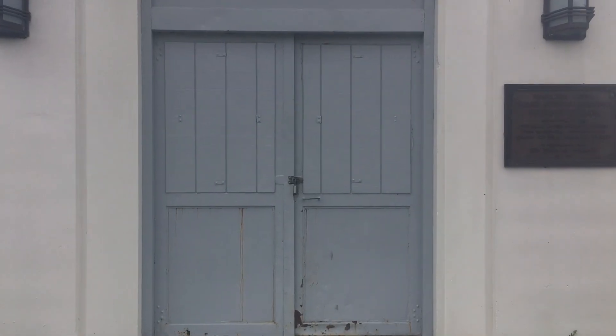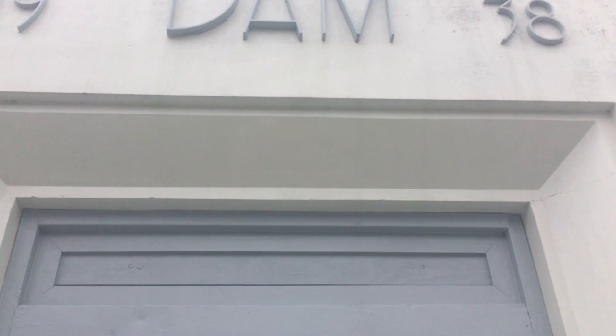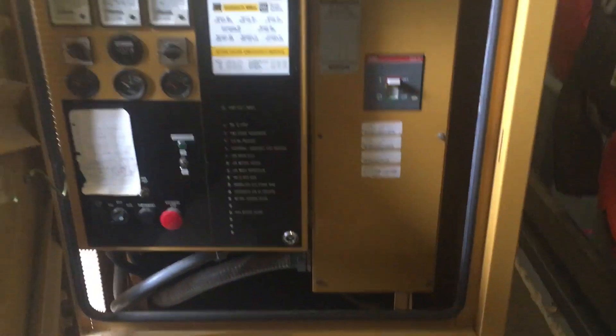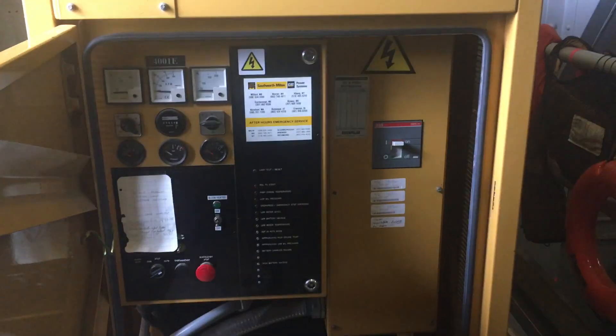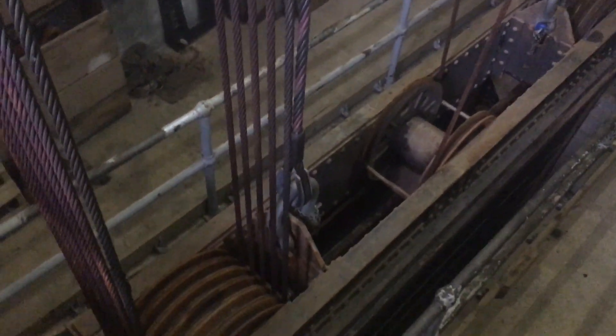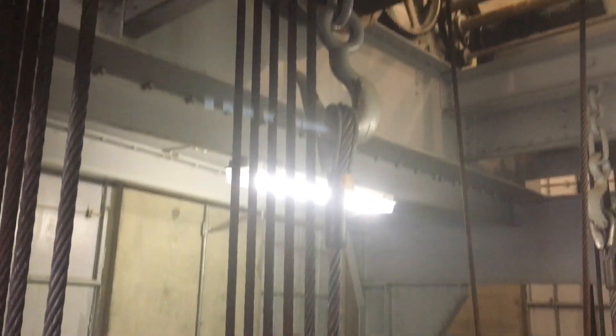This building on the crest is called the gatehouse, housing a diesel generator capable of 50 kilowatts. In the event of a power outage, the generator could operate the gates in the principal spillway, the vertical lift gate inside the gatehouse, and the well pumps. A vertical gate inside this building is responsible for controlling flow through the outlet tunnel of the dam to the power station below. The gate weighs over 40,000 pounds and takes one hour and 20 minutes to lower the 130 feet to the bottom and close the flow through the dam.